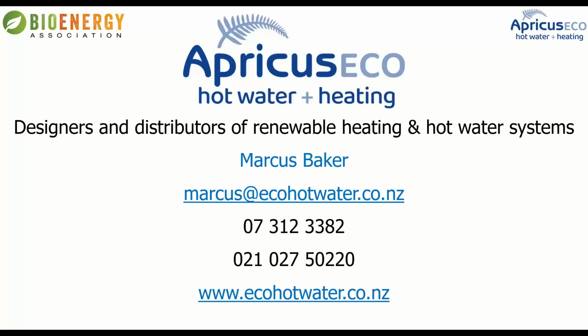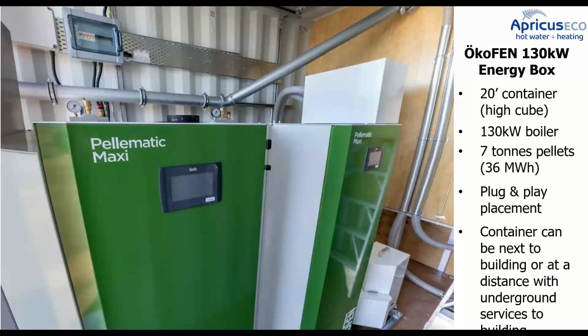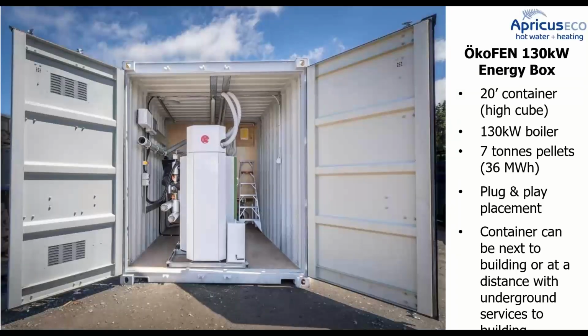What is the electrical power required to operate 130 kilowatts setting at full power? So, Robert, I'll just say it a bit more slowly. Electrical power. So for an ÖkoFEN boiler, the biggest draw is the fan unit that's going to pull the pellets into the boiler. In the most resilient scenario, you've got 2 of those fans, then at any one time it could be drawing 2.5 kilowatts of electricity, but that's only for about 5 minutes every day, maybe twice a day, if it's using a load of fuel, because that transfers all the fuel.